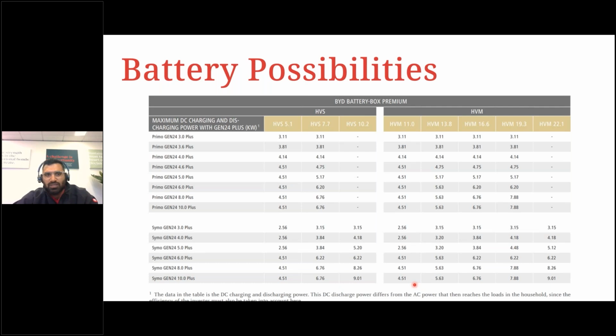Why is this something important to consider? If you are setting up a full backup circuit and the customer needs backup at nighttime, we are only limited by what the battery can discharge. So if you were to install an HVM 11 and the system goes into backup, the HVM 11 battery can only discharge 4.51 kilowatts. Over this, the system goes into overload trip. Similarly, here using an HVS 10.2 might be a better option because you can do up to 9 kilowatt discharging.